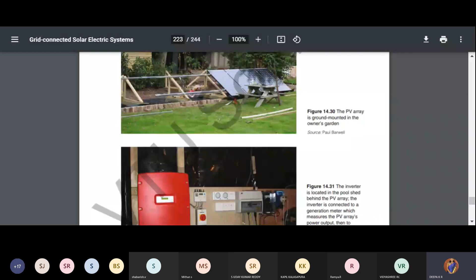We have an inverter, we have a digital meter, we have a switch controller, all these things. You can see the cables running here and there. So the inverter is located in the pool shed behind the PV array. So this is your inverter. The inverter is connected to a generation meter which measures the PV array power output. You can see the generation meter which is connected. Then a lockable double pole isolating switch, and you can see the double pole switch. You can put it to both the cases, and then directly into one of the miniature circuit breakers. Hope you can see the circuit breaker located on the distribution board in the shed. So here you can see the circuit breakers on the distribution board.